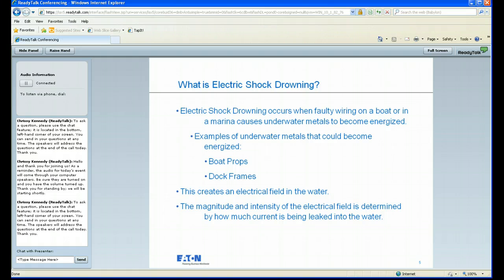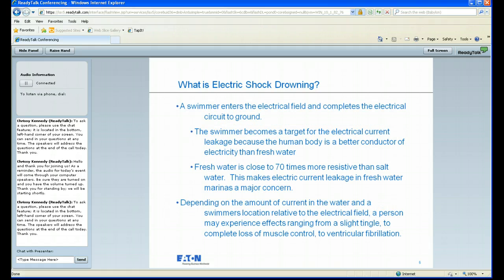The magnitude and intensity of these fields can be determined by how much leakage is in the water and how close your swimmers are to the cause of these leakages. Basically, a swimmer enters the water of an electrical field and completes a circuit. If you think of an electrical circuit as a large cycle, whatever goes out of an electrical source is going to come back through some lines that we'll show you in a little while, and anything that's not brought back in that cycle is going to be returned to ground. And we'll show you how an adequate system will be working compared to a faulty system here in a little while.